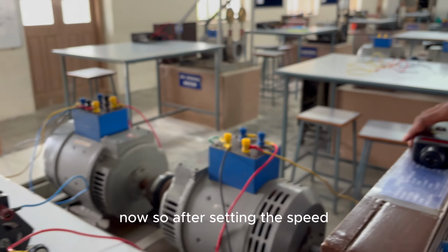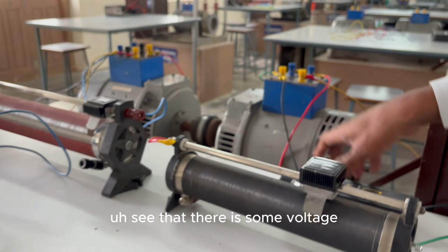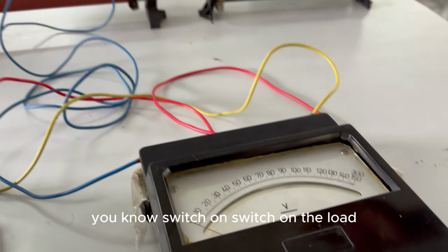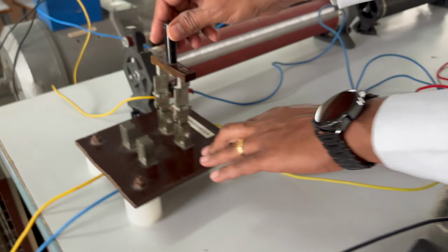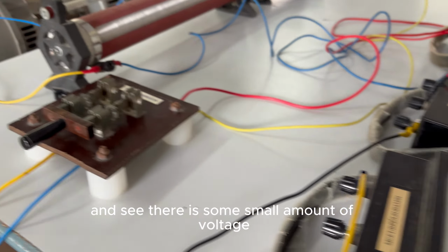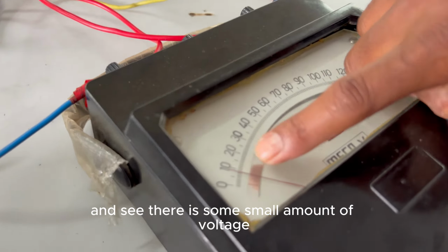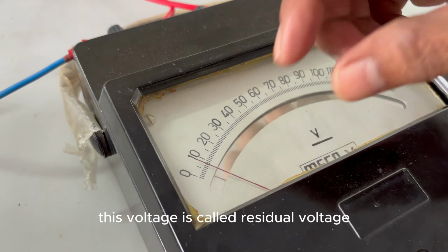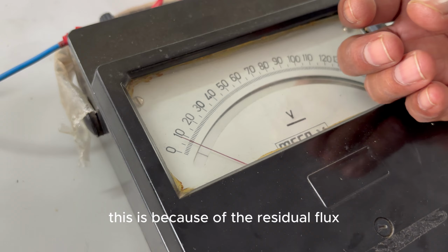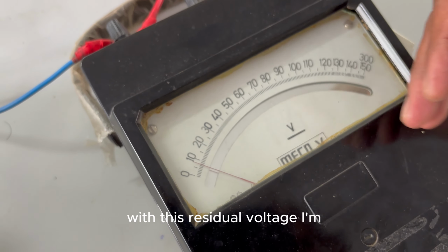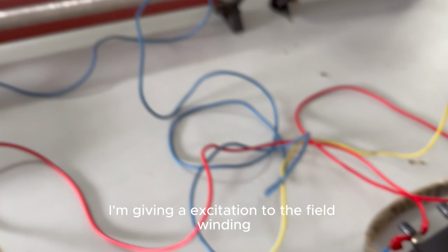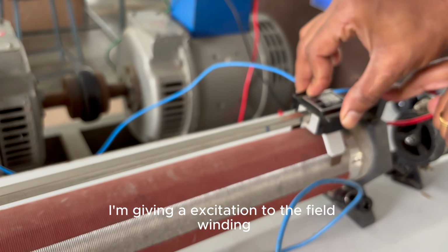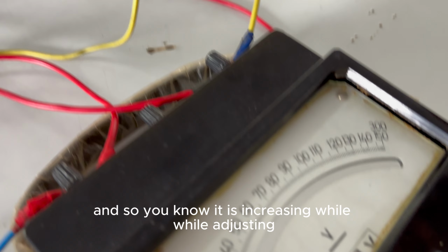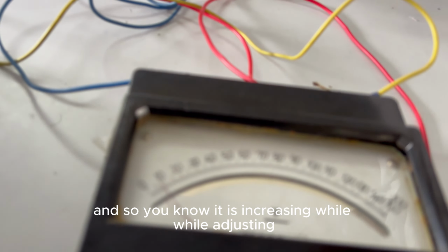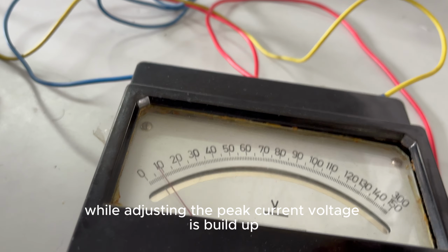After setting the speed, see that there is some voltage, and switch on the load. You can see there is a small amount of voltage. This voltage is called residual voltage, and it is because of the residual flux. With this residual voltage, I'm giving excitation to the field winding, and so it is increasing while adjusting the field current.